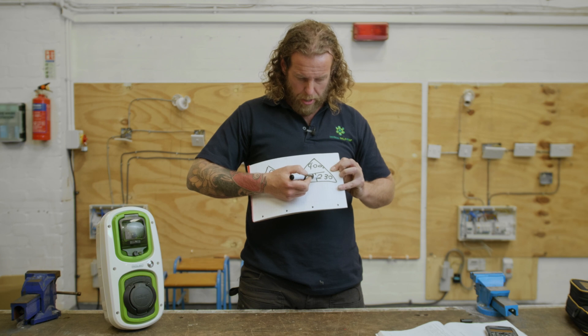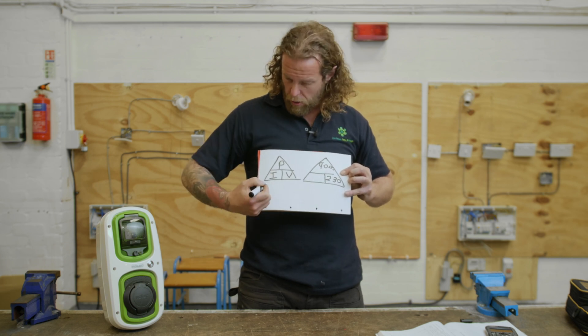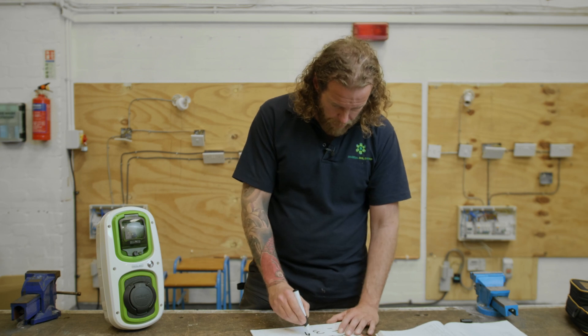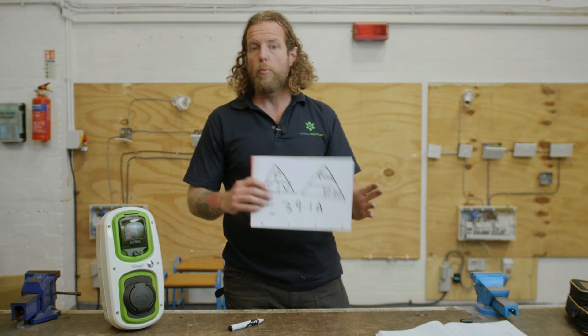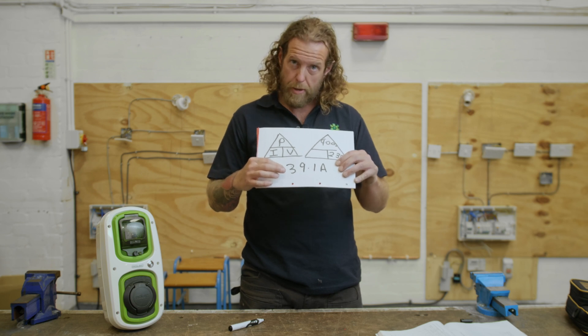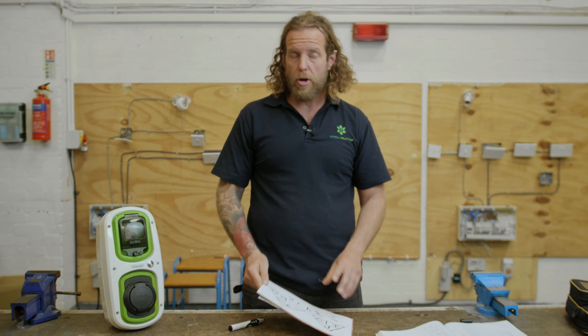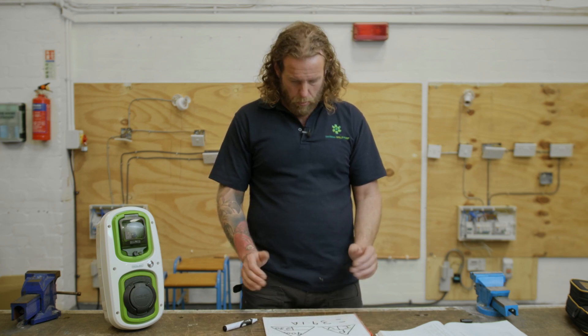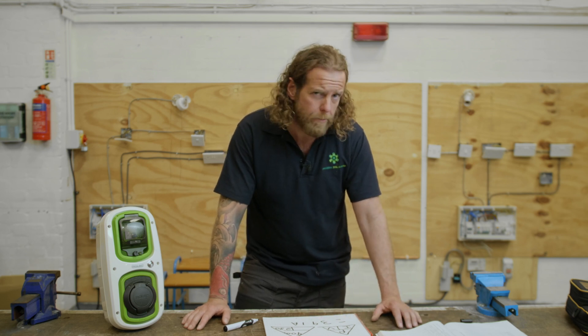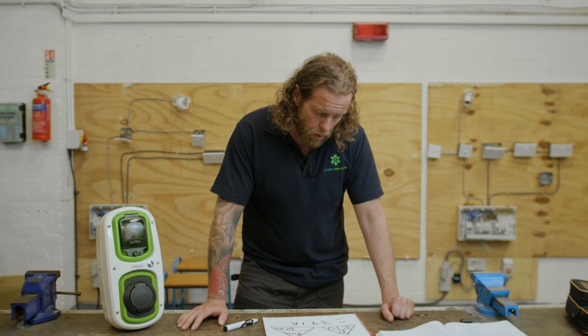So that would be nine thousand divided by 230, which gives us our missing figure of the amps. We work that out and it gives us 39.1 amps. So now we know our design current — we call this IB in electrical chat — our design current is 39.1 amps. We know that, and we do that as standard.